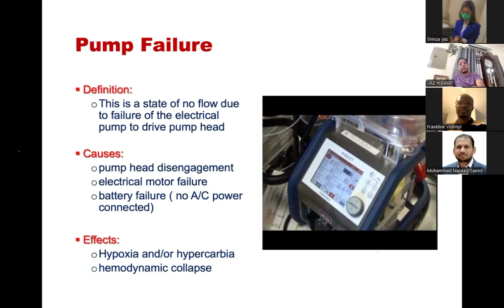So this is the effect of pump failures. What can be the prevention of pump failures? Number one, always maintain the pump head in a safe position. As I mentioned in the beginning, my presentation is purely for education purposes, and we are not going to highlight the name of any manufacturers or specific devices. As perfusionists, whatever console we are using, we should follow some prevention methods to keep our pump functional. So the first point is always maintain the pump head in a safe position.